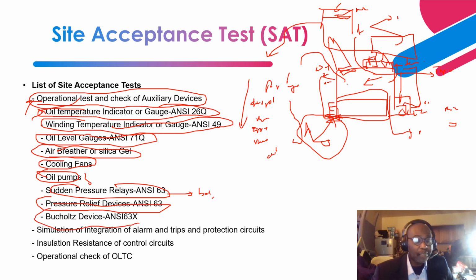Next is the Buchholz device, right? The Buchholz device is located in the downcoming piping from the conservator tank to the main tank, and it has three functions. The first one is to be able to detect low-level oil. If you run out of oil in the main tank and the conservator replenishes it, and this one runs out of oil at a certain level, it will give an alarm, and at low oil level, it will trip the transformer out of service.